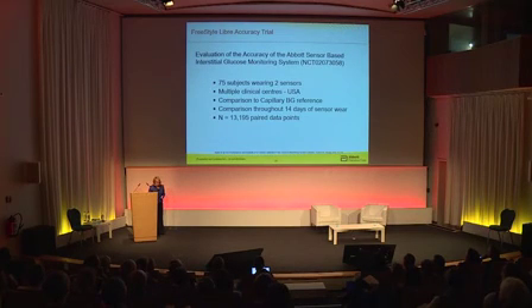So we know the sensor is stable, but is it accurate? And this is what the FreeStyle Libre accuracy trial looked at. This will be talked about in more detail. In this trial, there were 75 subjects wearing 2 sensors. It was conducted in multiple clinical centres across America. The primary comparison was to capillary blood glucose reference. The comparison was throughout the 14 days of sensor wear, and there were over 13,000 paired data points.